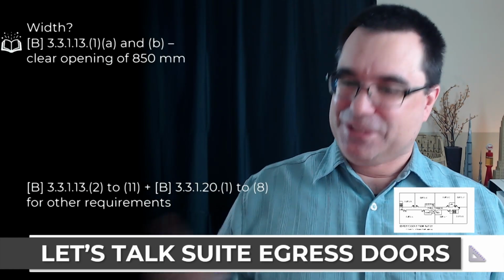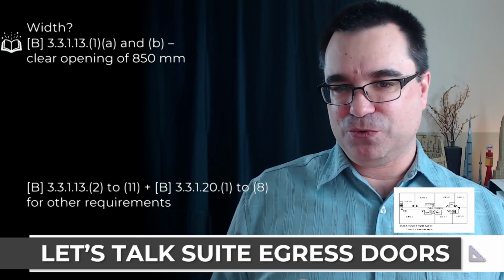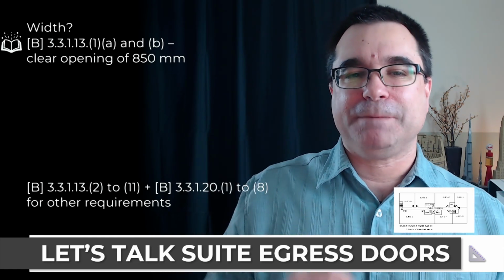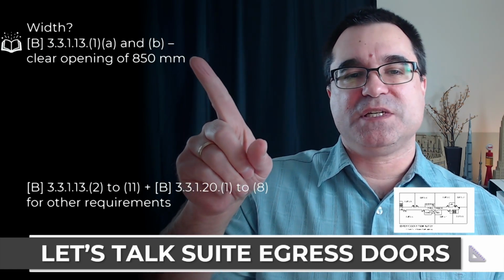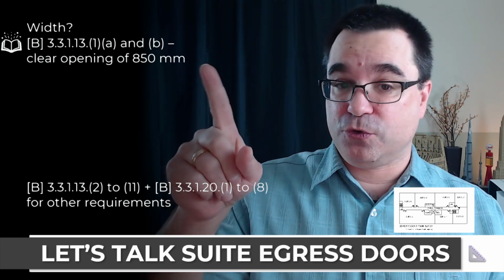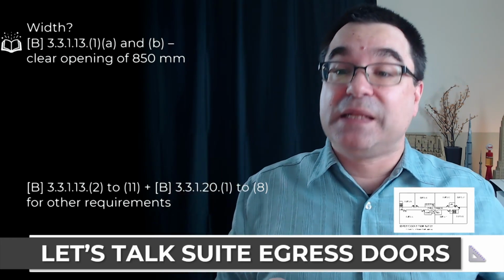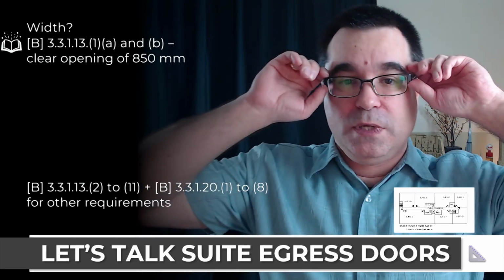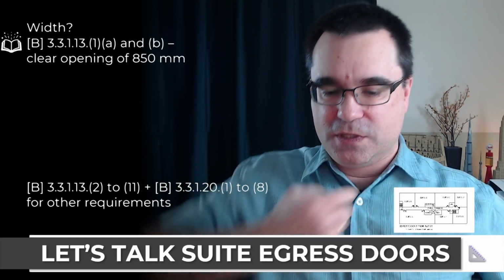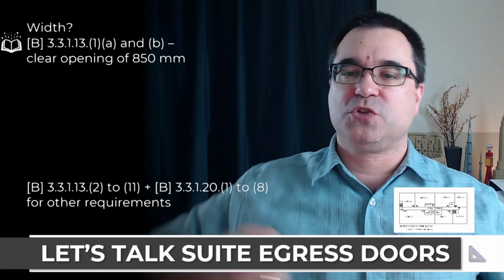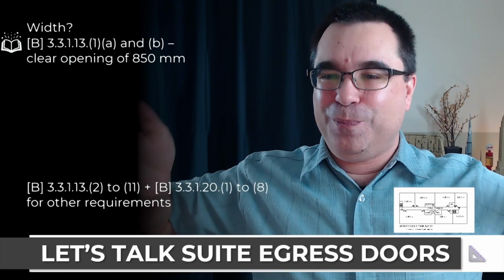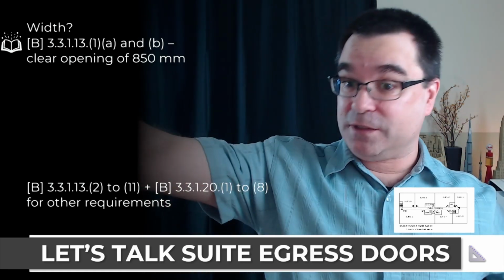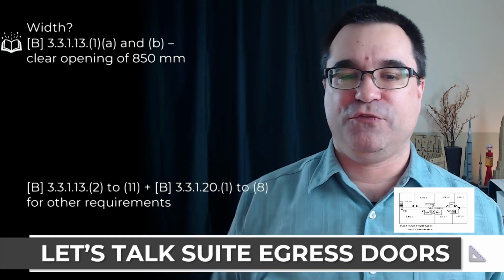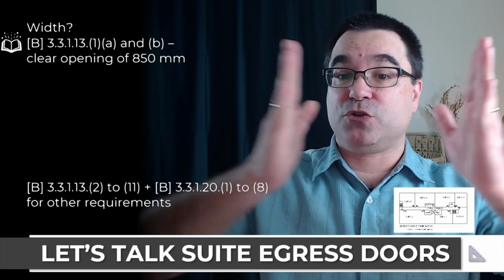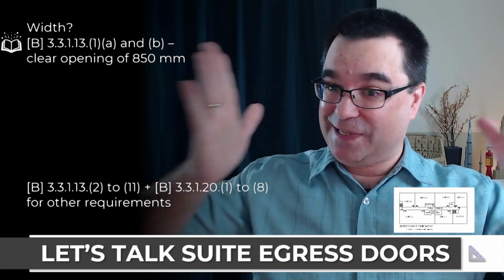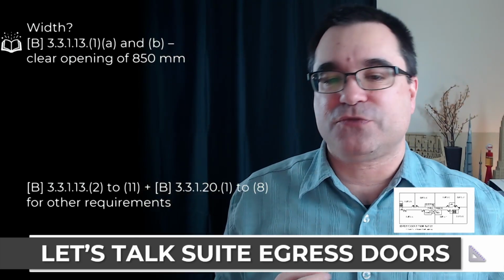Okay, so then let's talk about the width of egress doors. This is relatively straightforward. According to these two clauses, 3.3.1.13, 1A and 1B, the clear opening of a closure needs to be 850 millimeters. So when you open a door, whether it's push or pull, that clear opening, right, that when you get the door open, has to be 850 millimeters. So that means that the door actually has to be wider than that, right? Because when it opens, it allows for less room.